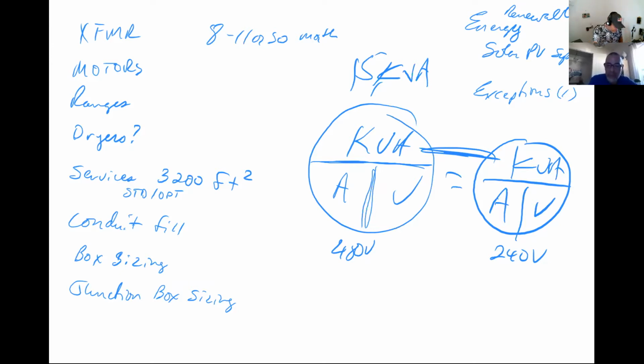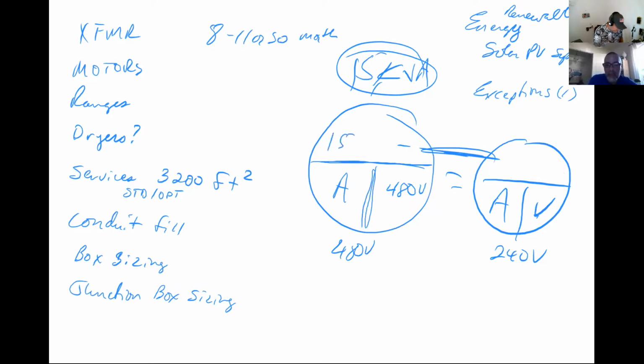I'm saying that number right here, this V, is actually going to be 480. And over here, whether they tell me this or not, they may give me an amp or a volt, doesn't really matter. If they give me this 15 kVA, which they almost always do, because that's what transformers are classified as, then I can take my little magic pencil and write in 15 right here and right here. So I've set myself up to keep it all straight. I would write 240 volts right there.